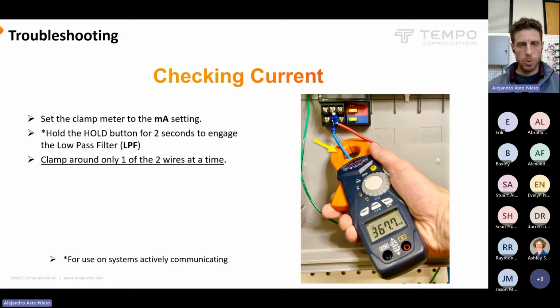And then you will want to clamp around only one of the 2 wires at a time on a 2-wire path. If you have the clamp around both wires, it's basically reading the average amount of current on those 2 wires. If there's current coming on one wire and going on the other, as voltage flips back and forth, it's going to read that as an average of 0. It's just going to tell you there's 0 current on that cable, which obviously is not true. The effects of the current moving in opposite directions on the 2 wires have a canceling effect. That can be helpful if you're trying to measure the amount of imbalance between the 2 wires. Let's say there's a ground fault on only one wire, it's going to use up more current.